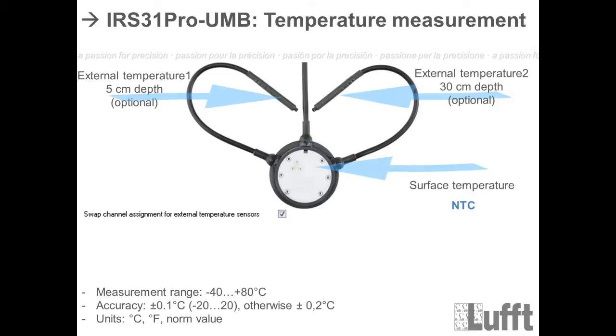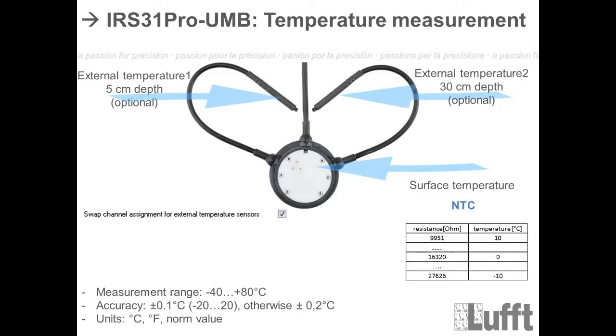For the temperature measurement, there are three temperature measurements depending on the version of the road sensor. The NTC surface temperature measurement element uses a negative temperature coefficient resistor: as temperature increases, resistance decreases and vice versa. At zero degrees Celsius, the output is about 16,320 ohms. It is a 5K resistor, meaning at 24.5 degrees the output is 5,000 ohms.